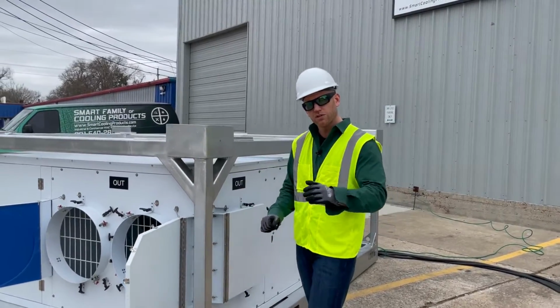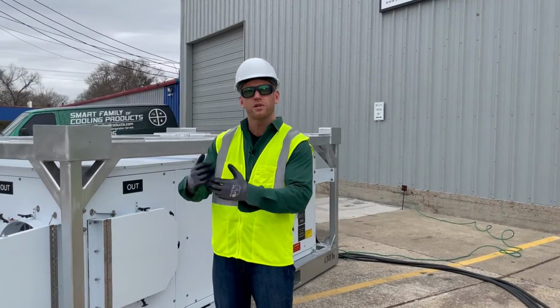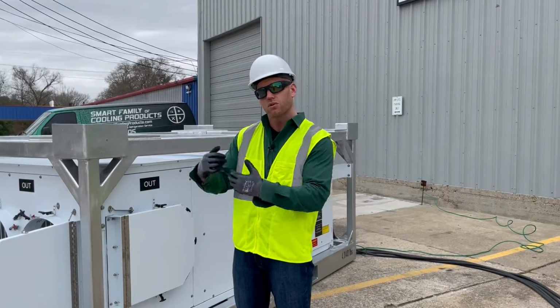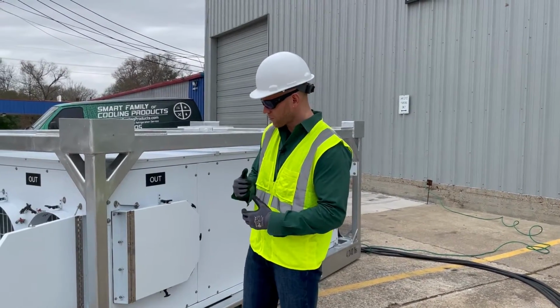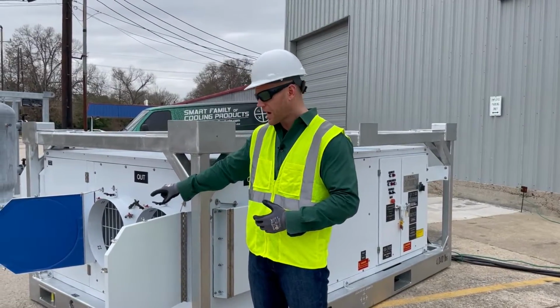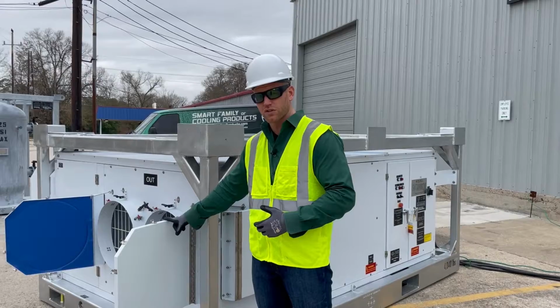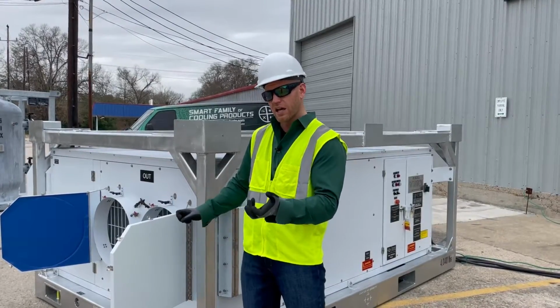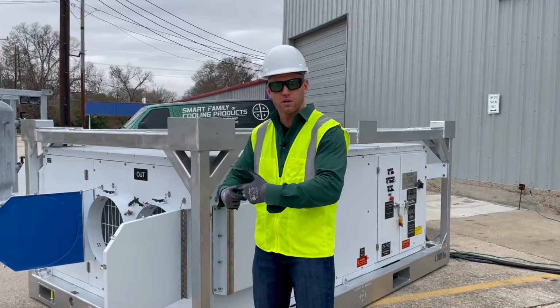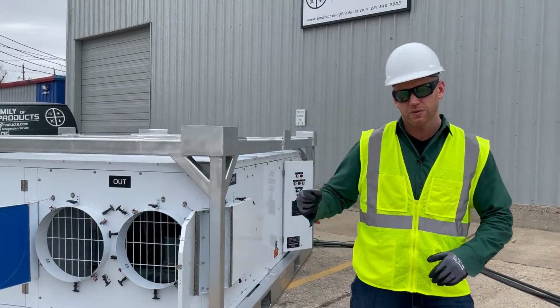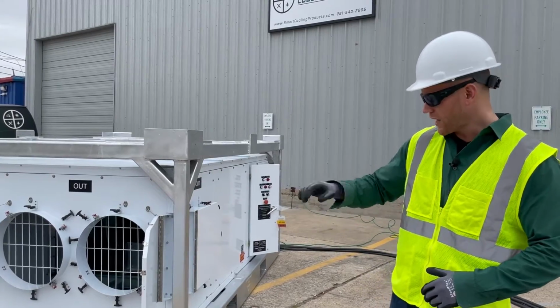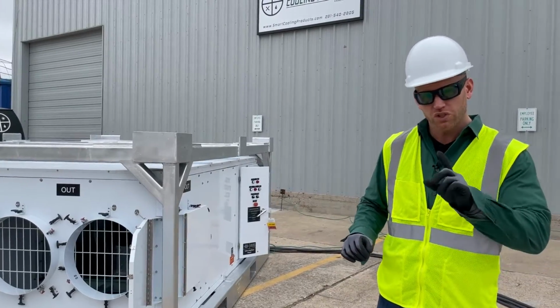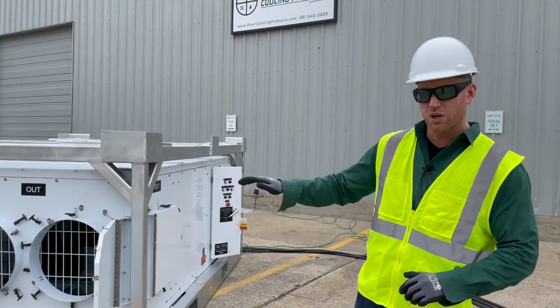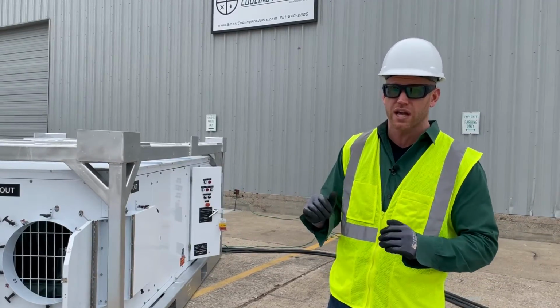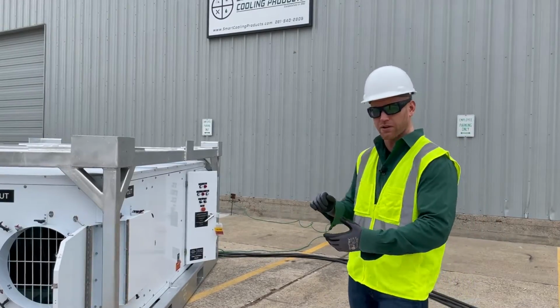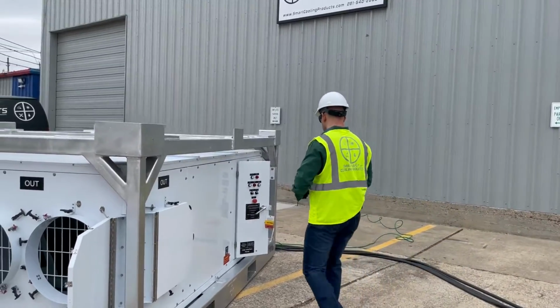The next step will be to adjust the speed potentiometer, or the blower speed pot if we're running in VFD mode, to the correct airflow and static pressure that the job site requires. So I'll go adjust this a little bit higher. I'll let you see the difference here on the discharge of the machine when I adjust that speed pot and give us a little bit more frequency and turn that blower a little bit faster. So now we've cranked up the speed pot, we've increased our airflow and our static pressure of this machine. What's unique about this particular machine is this unit will generate more than 10 inches of total static pressure. So this is a very, very high static model. I'm going to turn it down so you can hear me again.